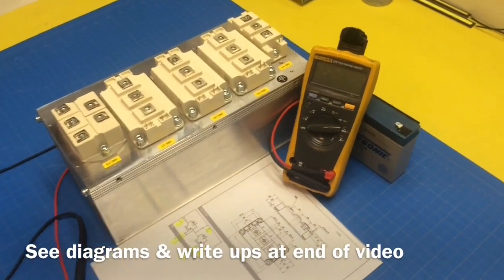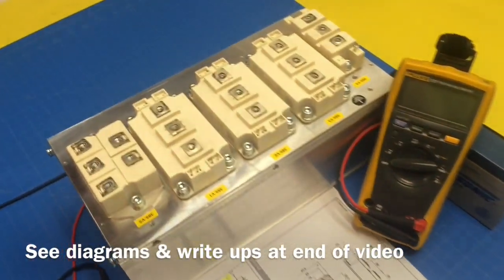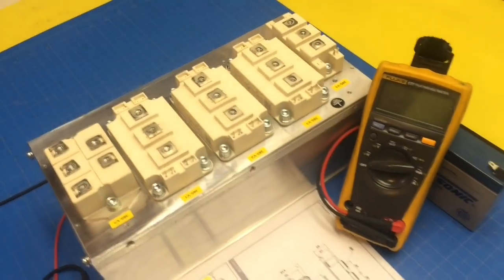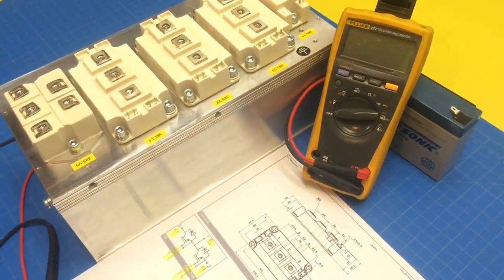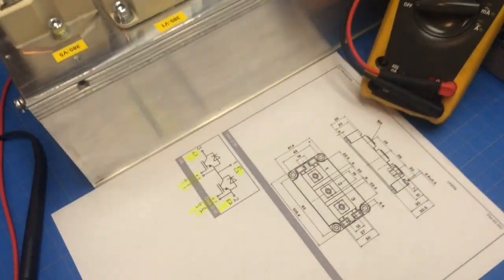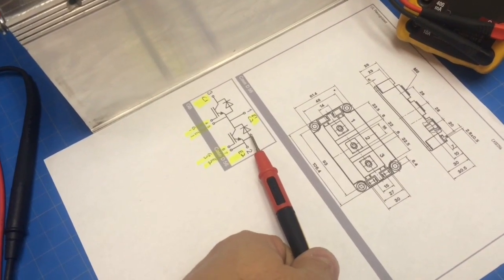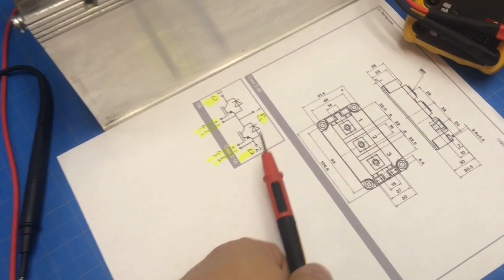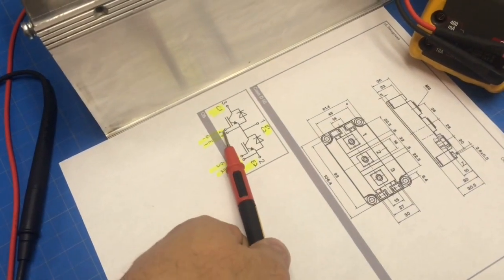Okay, now we're going to look at a meter test. This is helpful when these IGBTs are still in the circuit and you can't do the battery test. Basically, there's two things we can look at: this freewheel diode right here you can test on diode check, and we want to make sure these gates right here are not shorted.